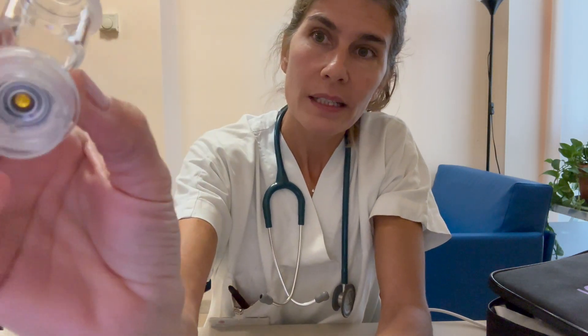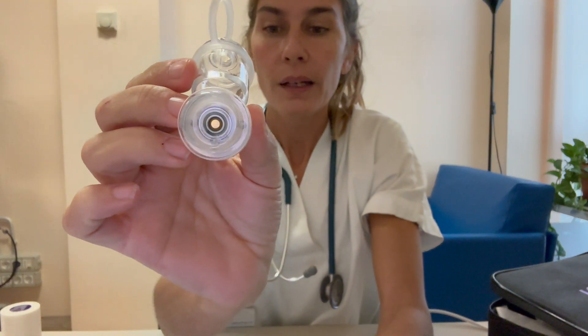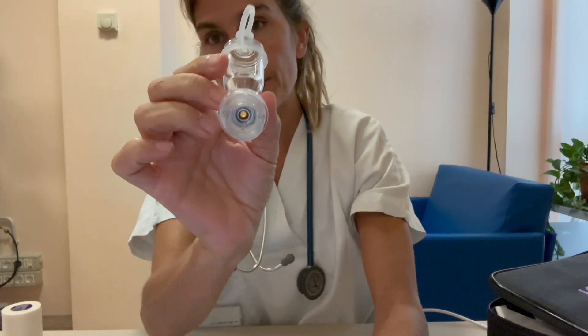This is really important in patients that cannot stop the non-invasive respiratory support but must do aerosols. Inside the medication cup is a polymeric diaphragm that makes the nebulization safe and with a high drug delivery rate.